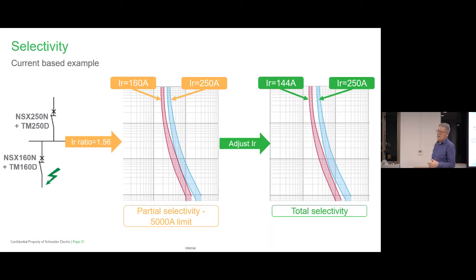I know most people don't select a 160 amp breaker or a 250 amp breaker, and it's fully loaded up to 250. We just know these things. So the odds are that you're going to be able to change IR. But if you're not, then you're going to have to do something about these two breakers if it's important to you that you've got total and not partial. Yeah, just to consider that.